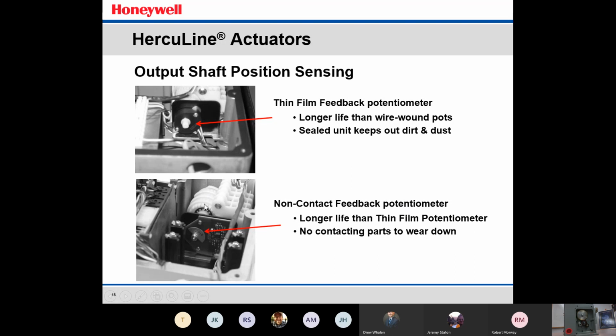Over on top of that thin film pot is the row of mechanical relays or switches that you can adjust by putting a flathead screwdriver into the top of this and rotating it so that the riser on the microswitch can actuate when you want it to during the stroke. This one shows, I think there's 4 switches there, and those are all 4 adjustable with the removing the top lid on the actuator.